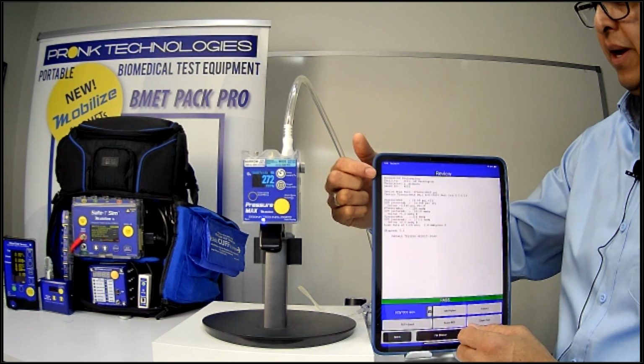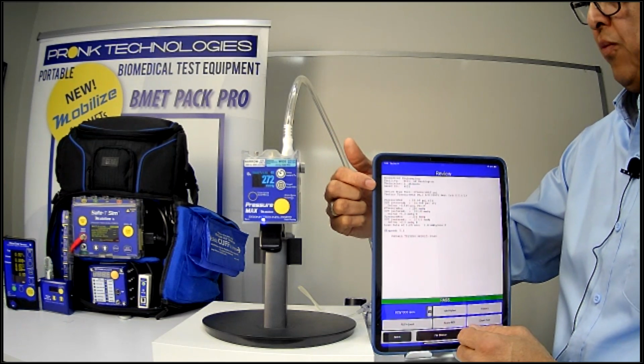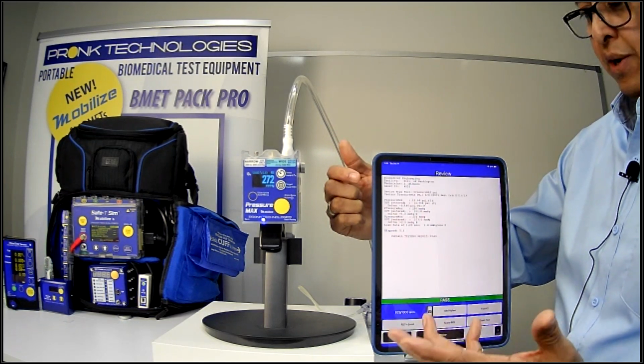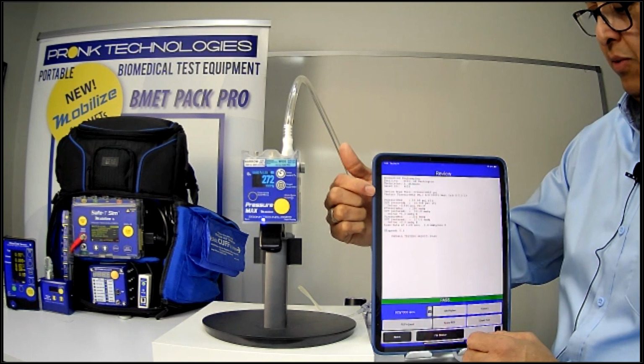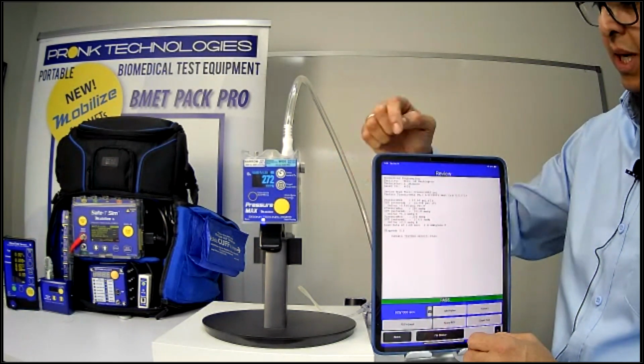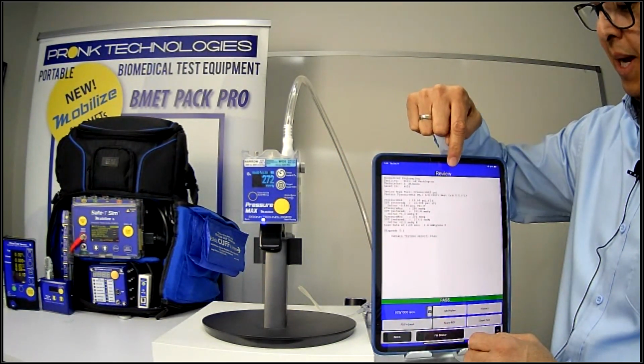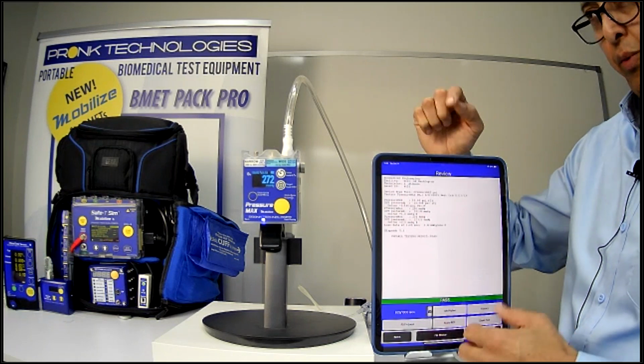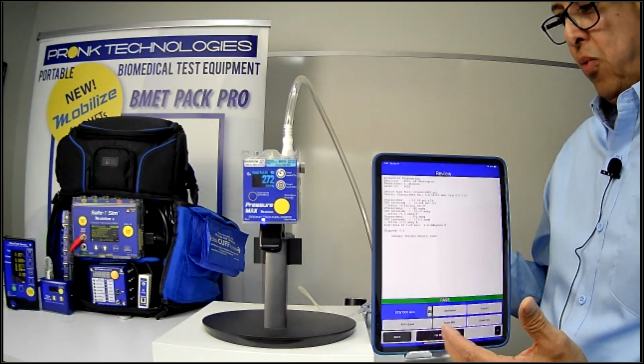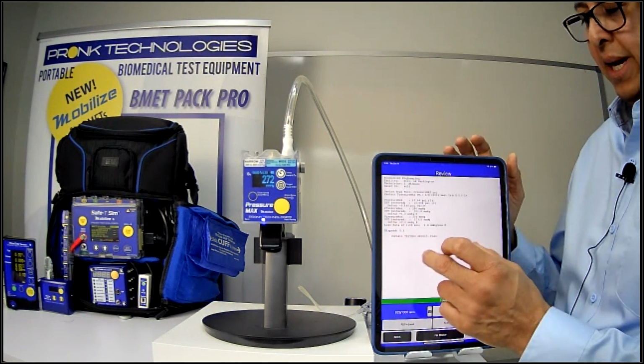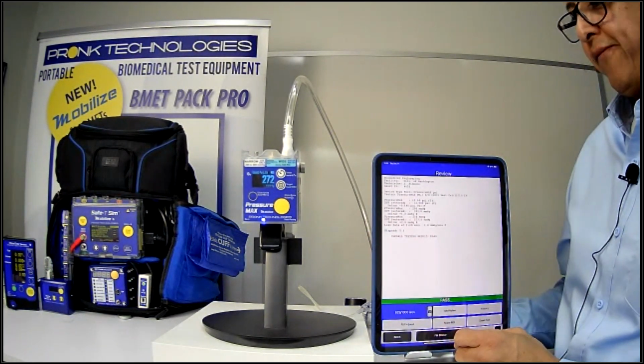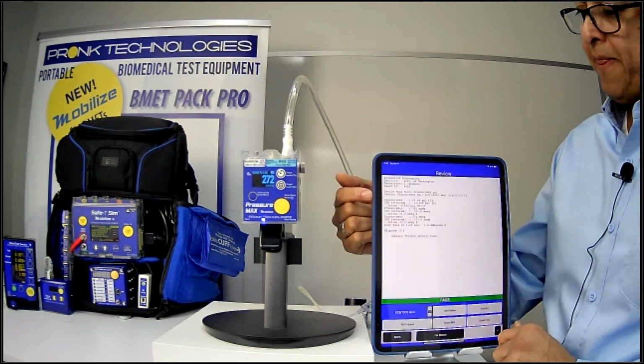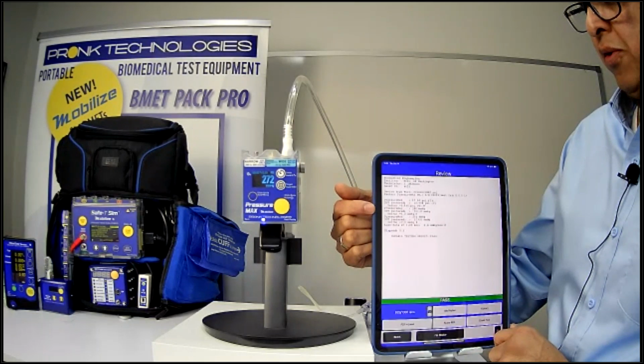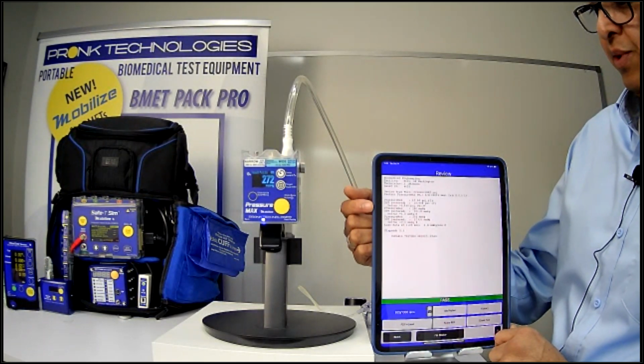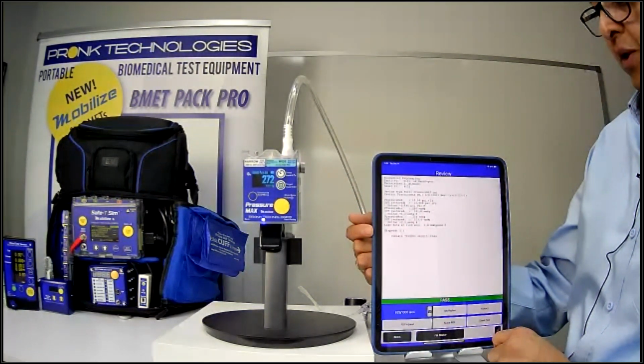At the top, you have your header information of what our facility, our organization is. You have the test equipment that was utilized, not only the test equipment, but the serial number and the date the test equipment was calibrated, which is very important. You want to know when the test equipment was calibrated, so why not have it on the report? That's important information to have on there. And then on the far left here, you can see all the test points that we tested with the results and the deltas that we saw.